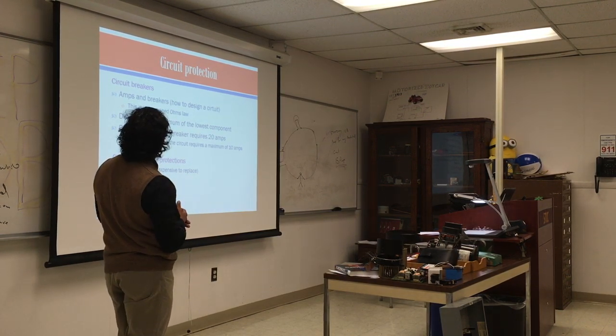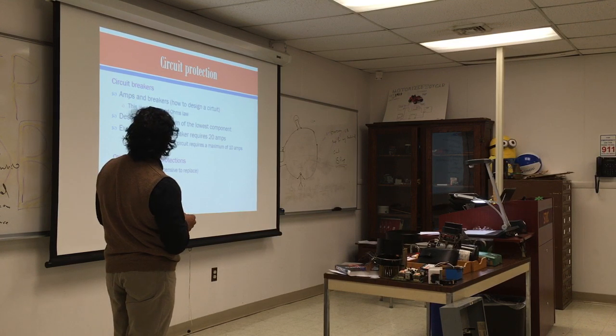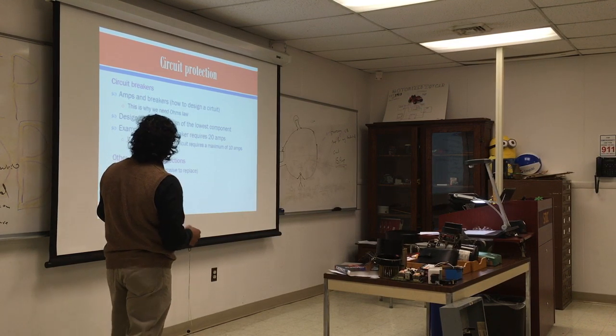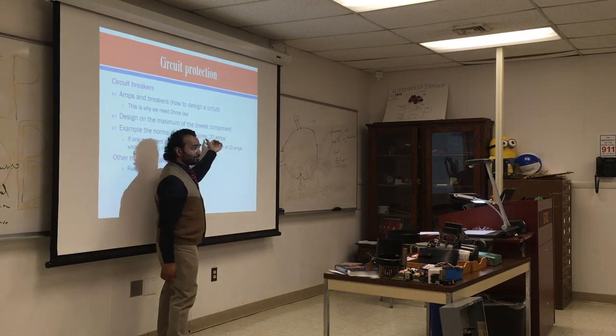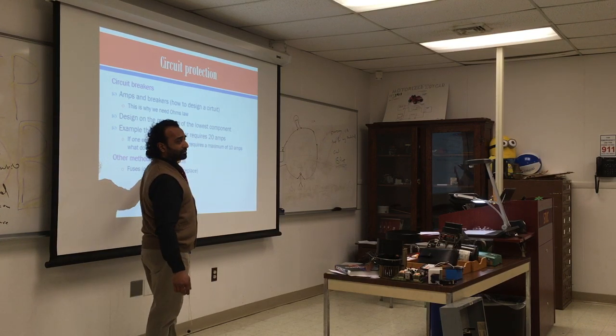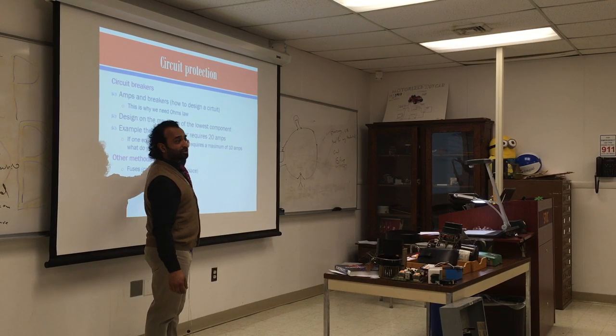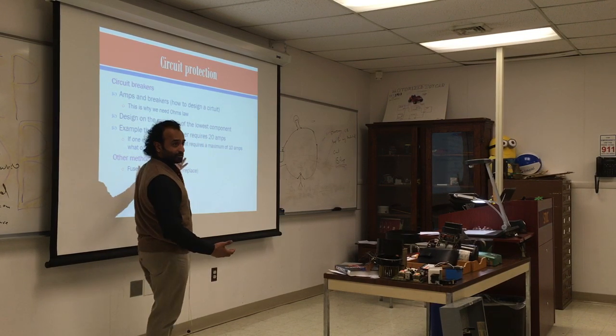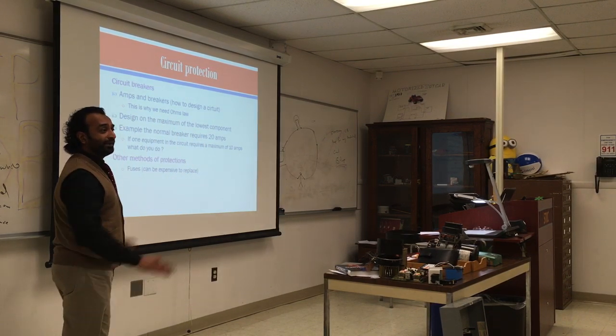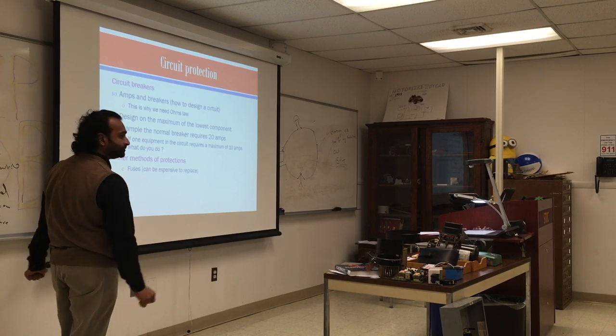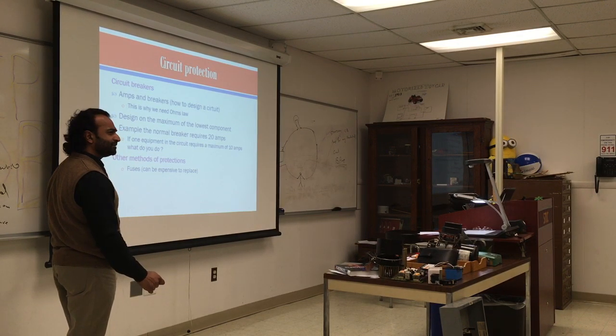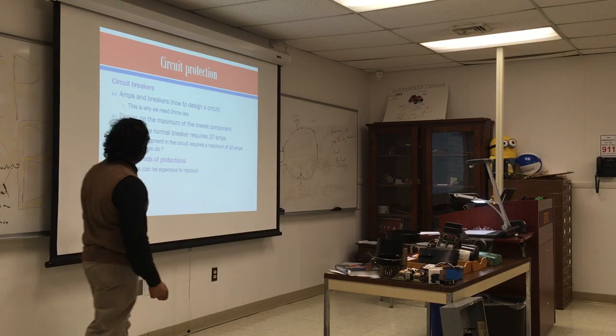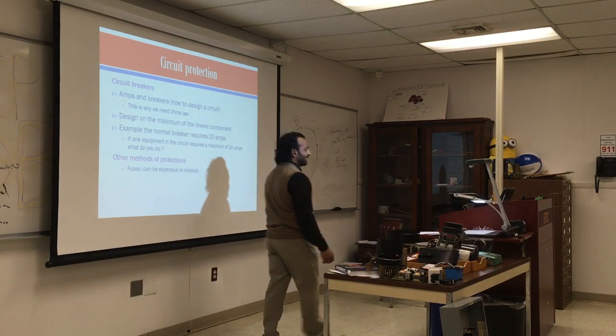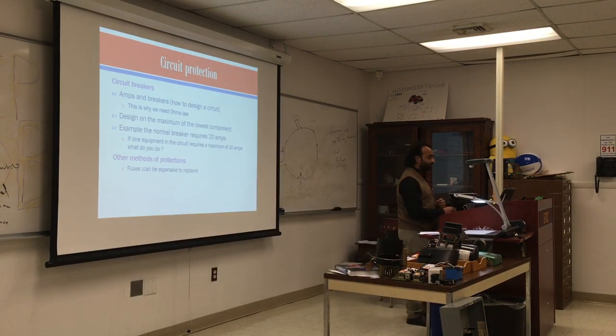Example, the normal breaker requires 20 amps. If you have the maximum at 20 amps and your component's maximum amperage draw is 10, it will burn before it reaches the circuit breaker. So that defies the purpose. You design for the lowest, weakest link in the circuit - make sense, a little bit? Okay, fuses can be expensive to replace, but they're necessary for some applications.